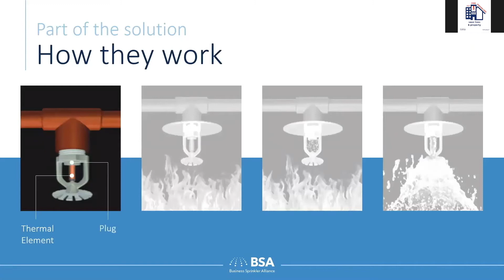That something happening is a fire. In a fire event, the sprinkler starts to heat up. Most importantly, there's a thermal element, a glass bulb filled with a temperature-sensitive liquid. As the fire ensues, that bulb heats up until it breaks. That sets off a chain of events which is quite simple: if that bulb is the only thing holding the plug in place, the plug is ejected, and then the water comes, projected onto the fire. It's as simple as that.